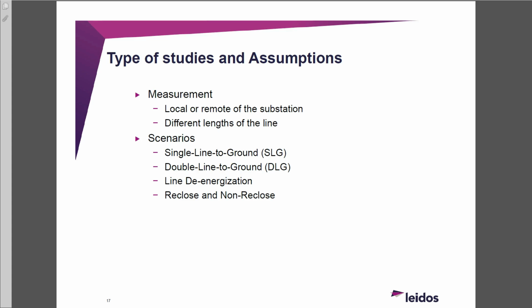The scenarios we did were single line to ground, double line to ground, line de-energization. One very important thing is reclose: high speed reclose and non-reclose. So we did those three - single line, double line, de-energization - for high speed reclose or without reclose. You'll see there's a huge difference in the TOV when you reclose the line versus high speed reclose.